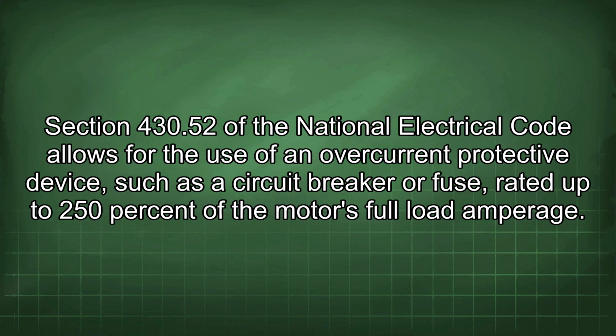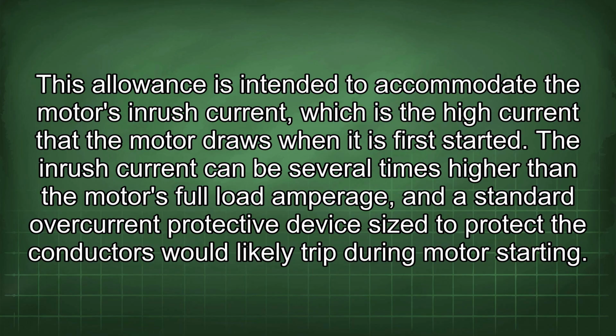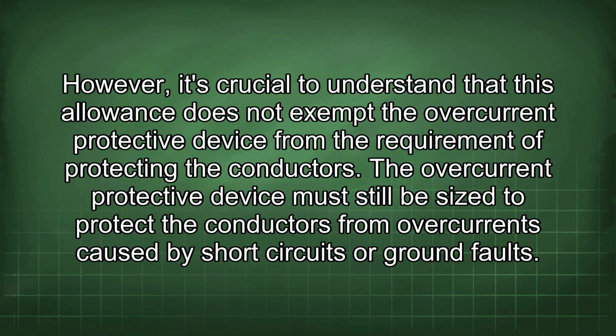Section 430.52 of the National Electrical Code allows for the use of an overcurrent protective device, such as a circuit breaker or fuse, rated up to 250% of the motor's full load amperage. This allowance is intended to accommodate the motor's inrush current, which is the high current that the motor draws when it is first started. The inrush current can be several times higher than the motor's full load amperage, and a standard overcurrent protective device size to protect the conductors would likely trip during motor starting. However, it's crucial to understand that this allowance does not exempt the overcurrent protective device from the requirement of protecting the conductors. The overcurrent protective device must still be sized to protect the conductors from overcurrents caused by short circuits or ground faults.